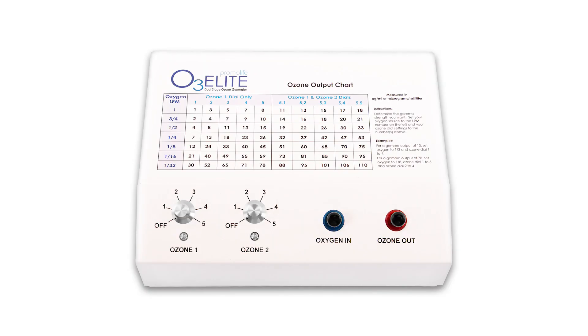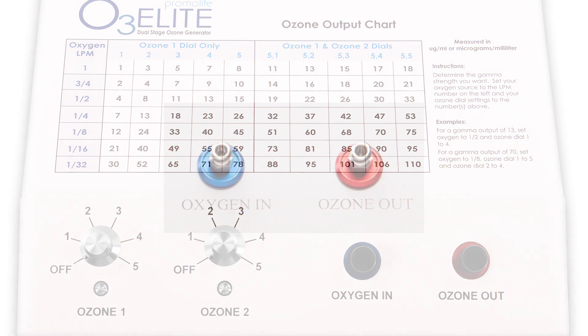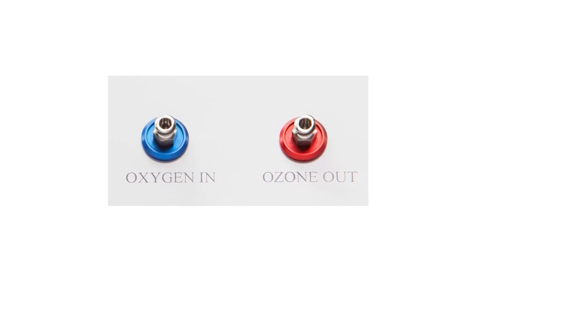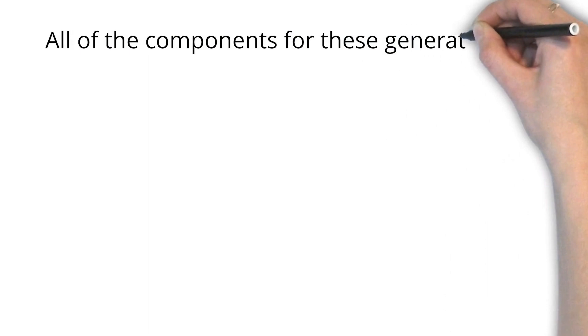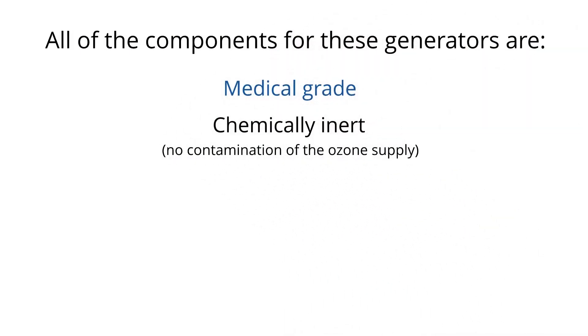Some similarities of these generators are that they come with a thick aluminum case with no plastic components inside and 316 stainless steel Luer-lock fittings. These allow you to securely connect the tubing to the generators, eliminating any chance of tubing becoming loose, falling off, or having an ozone leak. All of the components for these generators are medical grade and chemically inert, which allows for no contamination of the ozone supply.